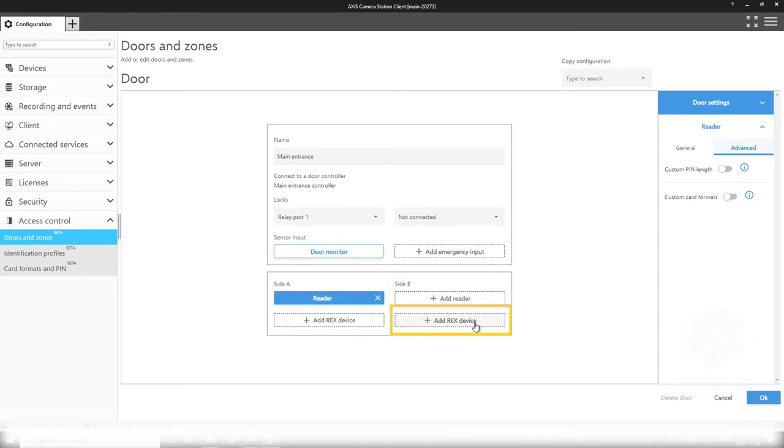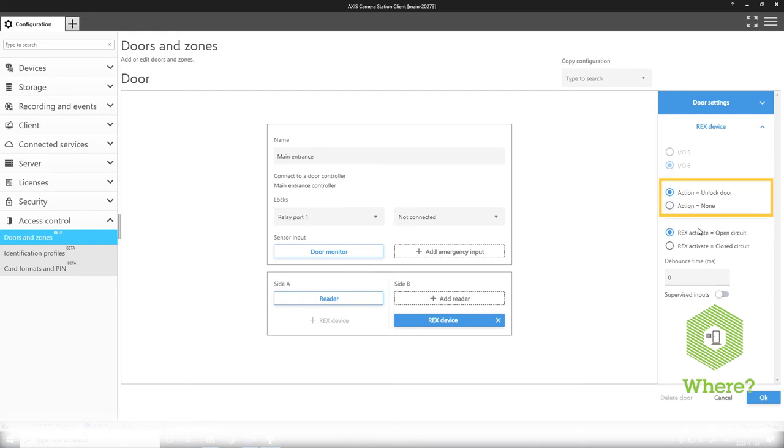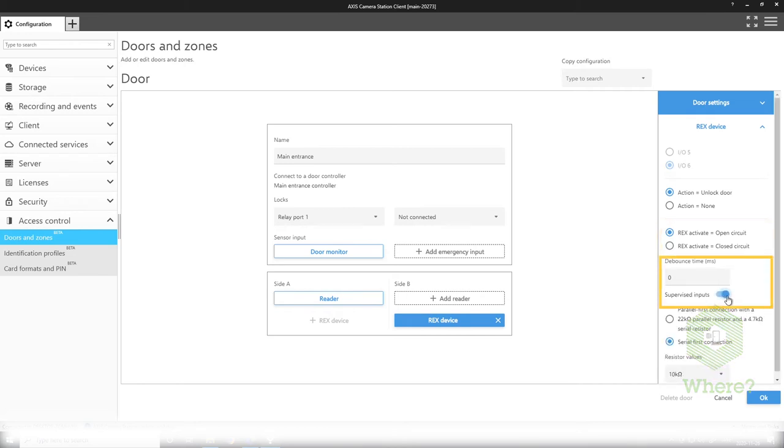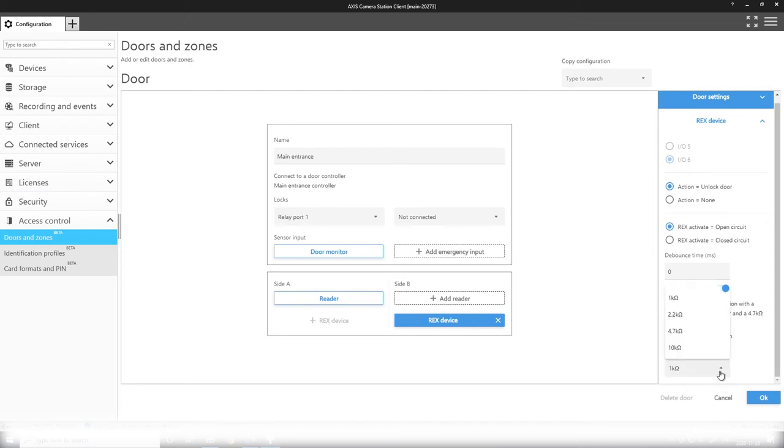Next I add a REX device to the B side of my door and here as well you can see that I can choose if the REX actually unlocks the door or if it is just an exit notification. I select the polarity of the REX and possibility to add debounce time and supervised inputs. Supervised input settings are the same for REX, reader, or door monitor where you can have either the parallel resistor connection or a serial resistor connection and select the resistor values, same setup as you have in the A9188 for instance.